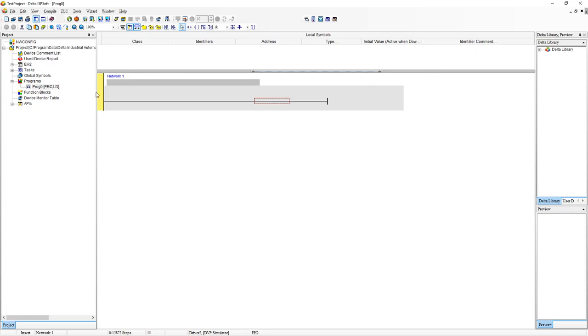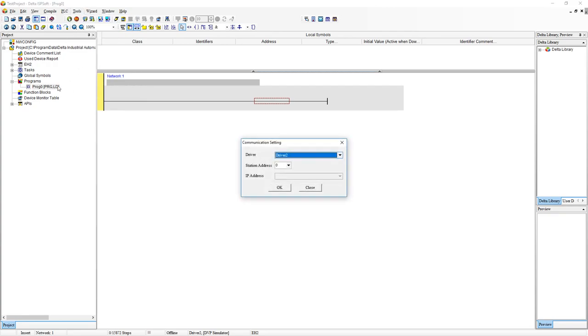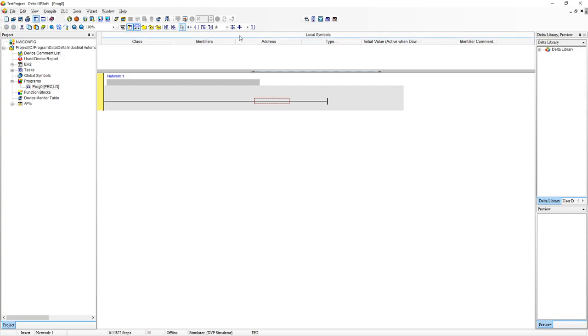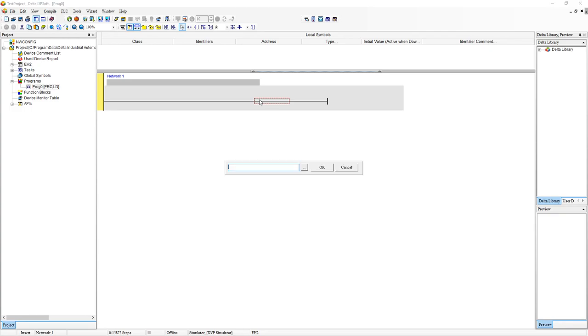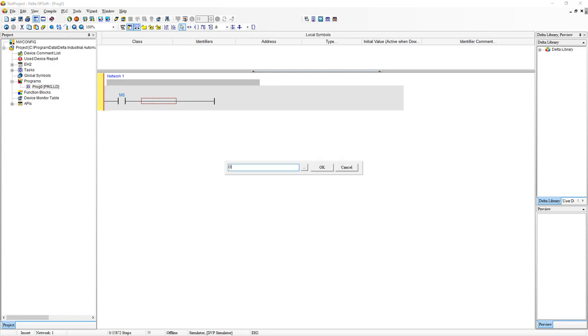The first thing we want to do before we start writing any ladder code is to make sure that our communication settings are correct and that we've got it allocated to our simulator. Ok, now I can actually start typing out our program. First, click on the first rung. Press space bar, type LD M0. So this will be our input. Click again, space bar, out M1.